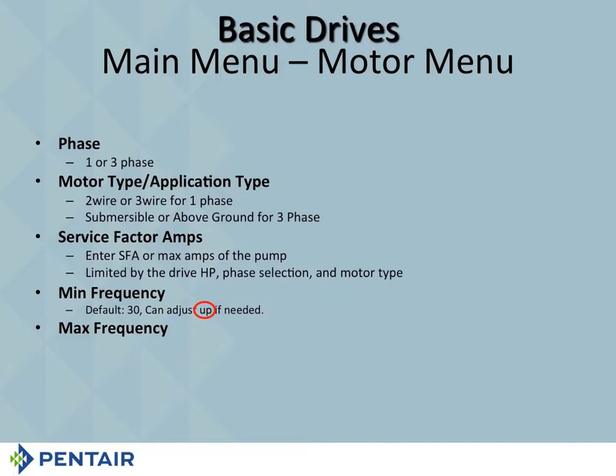We get asked that question all the time. The answer is no. It was originally designed for submersibles, and 30 is the minimum. Maximum frequency is 60. Remember, when you're doing single phase, that's it. It won't even ask you, do you want to go up? If you pick 3-phase, it will allow you to go up to 80 if you pick submersible. If you didn't pick submersible, it won't let you go up to 80 there either.